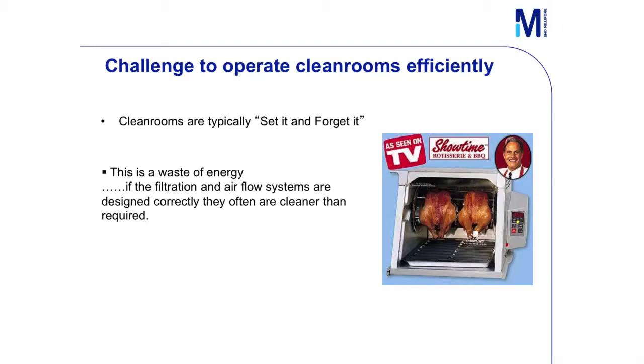I joke around a little bit and say clean rooms are typically set it and forget it. You build it, you commission it, and you walk away. It's kind of like the Ronco cooker, right? You set it and you forget it. Well, it's a big mistake. It's a huge waste of energy. The filtration and airflow systems are often designed so that the clean room is cleaner than it needs to be. For instance, if we're not making the Mobius bags on the weekend, why do you need to run all that air? Slow it down.